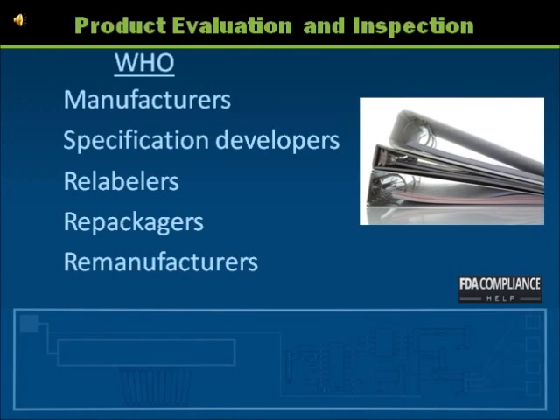Product evaluation is required by the FDA Quality System Regulations and GMP. The device manufacturer, specification developer, remanufacturer, relabeler, or repackager must show, with documented evidence, that a component, in-process unit, or completed device was processed according to the device master record and meets all of the acceptance criteria and specifications.